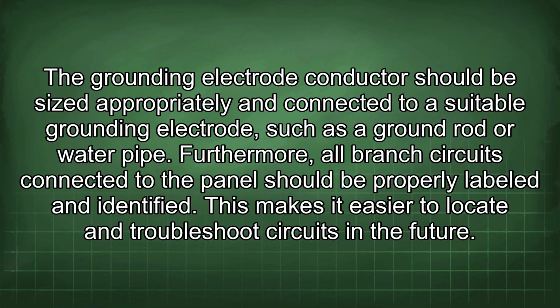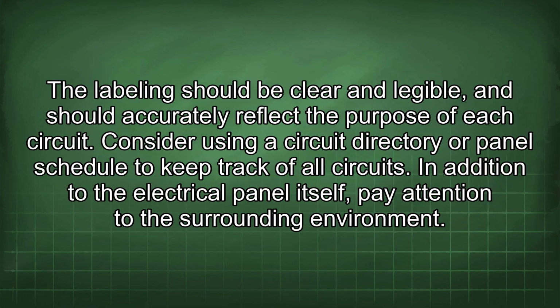The grounding electrode conductor should be sized appropriately and connected to a suitable grounding electrode, such as a ground rod or water pipe. Furthermore, all branch circuits connected to the panel should be properly labeled and identified. This makes it easier to locate and troubleshoot circuits in the future. The labeling should be clear and legible, and should accurately reflect the purpose of each circuit. Consider using a circuit directory or panel schedule to keep track of all circuits.